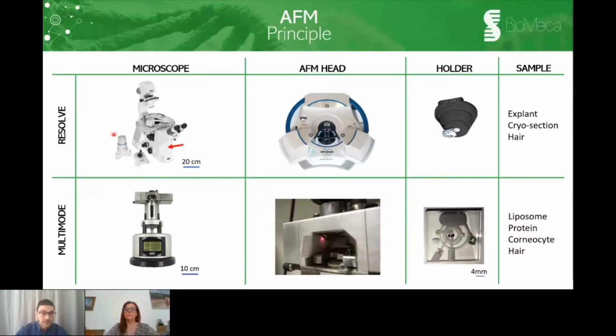As you can see in this picture, we have different parts on the AFM. The first part is the optical microscope with a fluorescence system, and we use it for the transparent sample and the fluorescence sample staining. Then there is the acquisition plate with less than 1 nanometer precision to move the sample in the XY axis. Here there is another camera with a LED for opaque samples, and we put the camera on the head of the AFM. And finally, the head of the AFM, with the magnification here for the Resolve and here for the Multimode. And at the center of the head, we can find the holder where we put the cantilever.